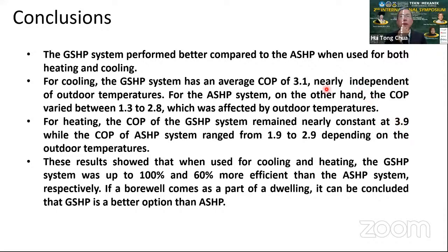Now you can see that in cooling mode, the air source heat pump, in contrast, delivers a COP of 1.3 to 2.8 as against 3.1. And for heating, the air source heat pump delivers 1.9 to 2.9 depending on the outdoor temperatures. So in conclusion, the ground source heat pump can be up to 100% more efficient than the air source heat pump in cooling mode, and 60% more efficient in heating mode.